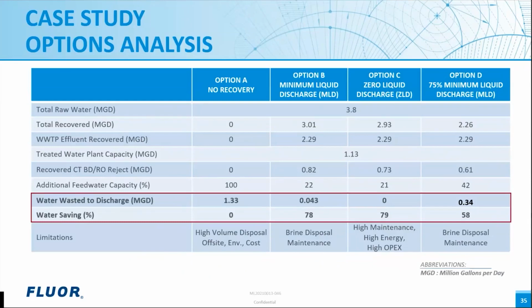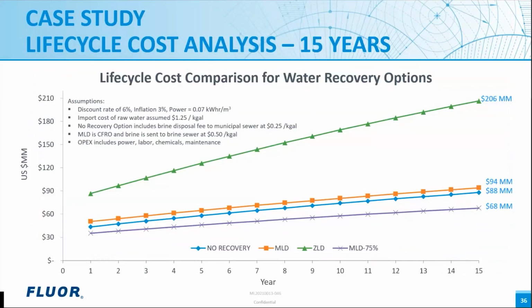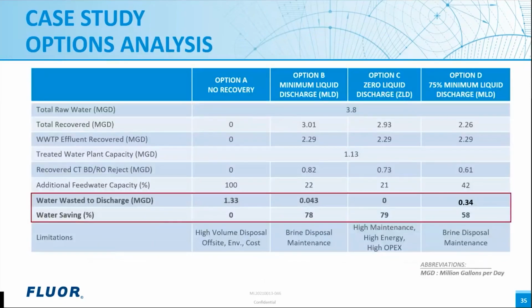Note that between the 4 cases, water savings between option B and option C are most similar because the MLD system operates at a high recovery based on this plant's particular water chemistry. The limitation for no recovery option A is that large amount of treatable water is discharged off-site that could negatively impact the environment and has an associated disposal cost. The ZLD system limitations are high CapEx and OpEx, complex operation, and high maintenance. MLD options have the limitation of discharging a small volume of brine stream. Maintenance from scaling and fouling of the MLD system is a limitation that needs further close attention.